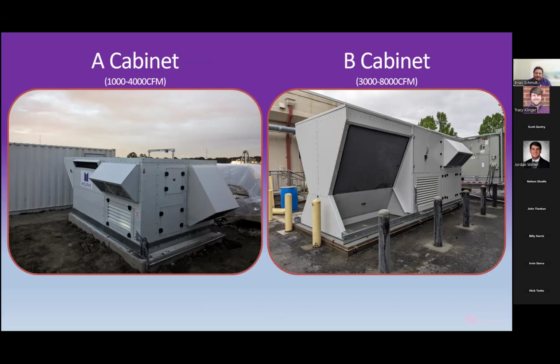These are slightly longer than a comparable DOAS system with hot gas reheat, not by much, but they are a little bit heavier. They're about 10%, maybe 15% additional weight. So if it's going on a roof, that's certainly something to think about structurally. If it's going on the ground, not quite so much of a concern about weight, but again, it could be a little bit longer than you might traditionally be accustomed to. The reason for that is we need the space for the absorber and the desorber pad.